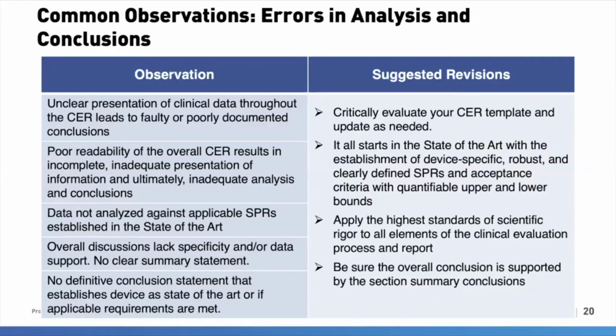Many of our gap analyses observations have to do with presentation and organizational issues that are built right into the CER itself. Unclear presentation of clinical data, which may result in faulty or poorly documented conclusions. Poor readability, which is also directly related to the unclear presentation of information. This can result in inadequate analyses and, again, faulty conclusions. All data sets may not be analyzed against applicable SPRs and acceptance criteria. Discussions lack specificity or data support, or clear summary statements may be missing. And finally, there is no summary conclusion statement that establishes the subject device as the state of the art, and/or that all applicable requirements have been met in this evaluation. Those are two critical bottom line statements that should be in every CER.